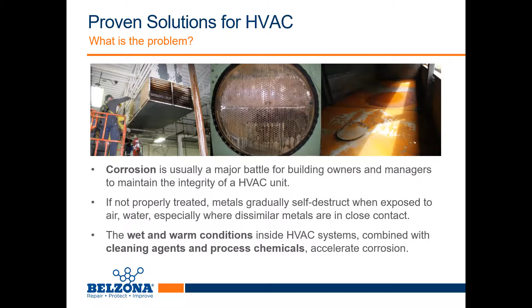What is the problem? Corrosion. We're going to look at a couple of them. What are these main problems? Condensation weakens and corrodes the metal surfaces, leads to breakdowns in the structure and subsequent structural and operational failure of the HVAC system. Water temperature is something to consider. Chemical reactions proceed faster in hot water, as we know. As the water heats up, more oxygen reacts with the electrons and water at the cathodes, forming hydroxides. Usually a rule of thumb is that for every 18 degrees Fahrenheit increase in temperature, you're going to get increased damage of this type.